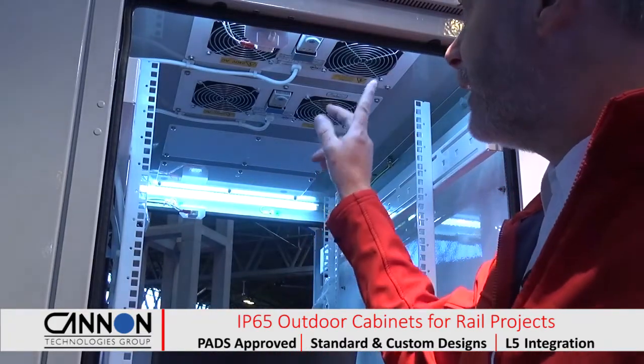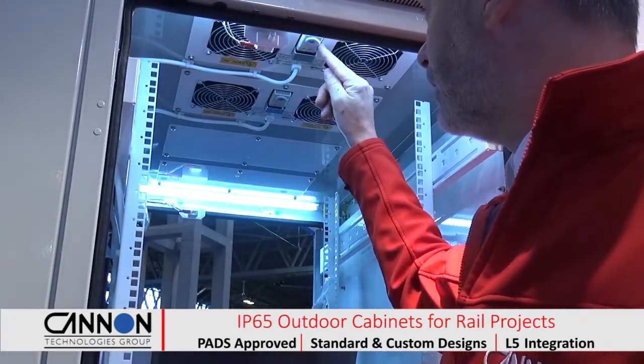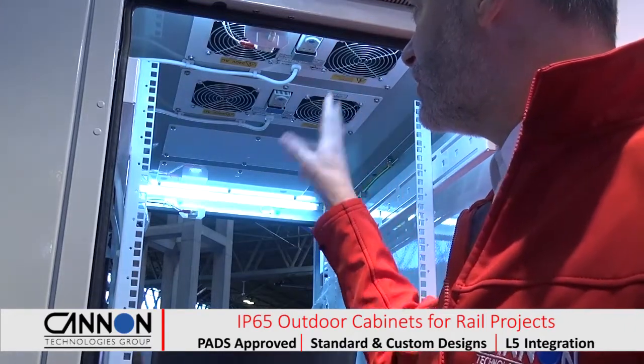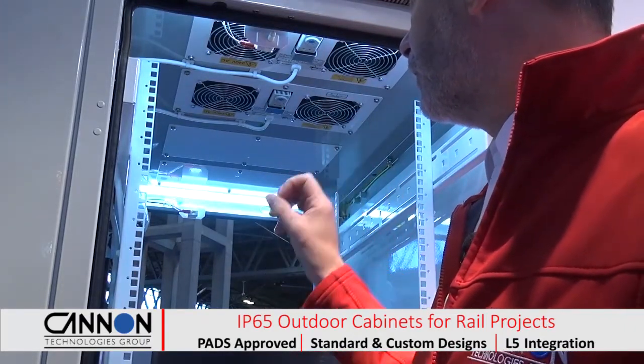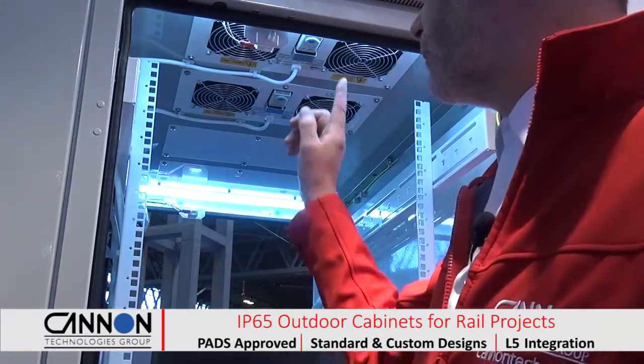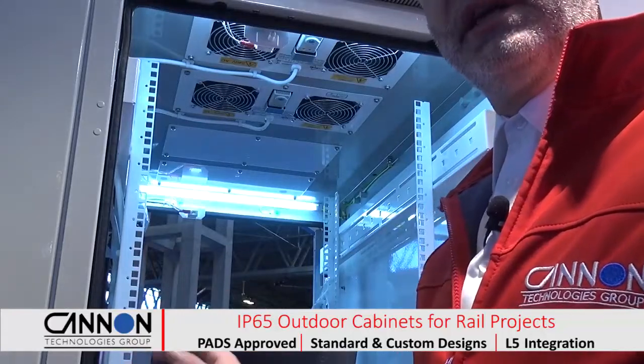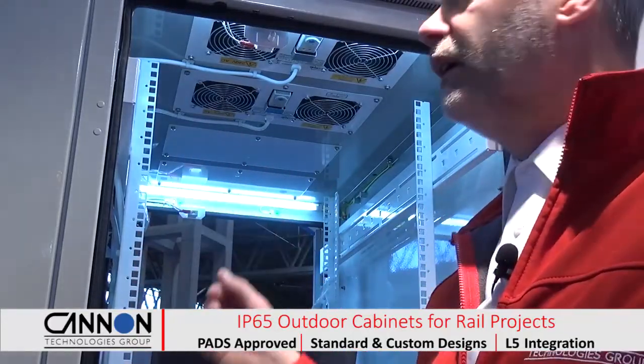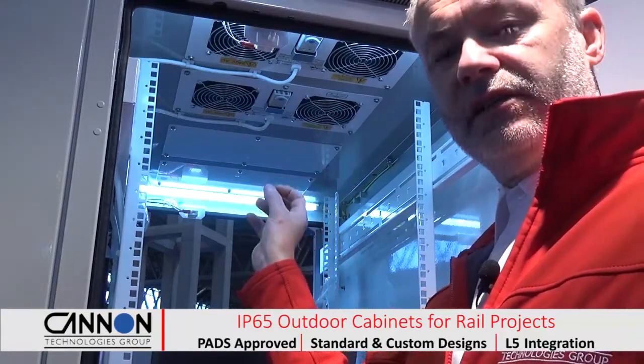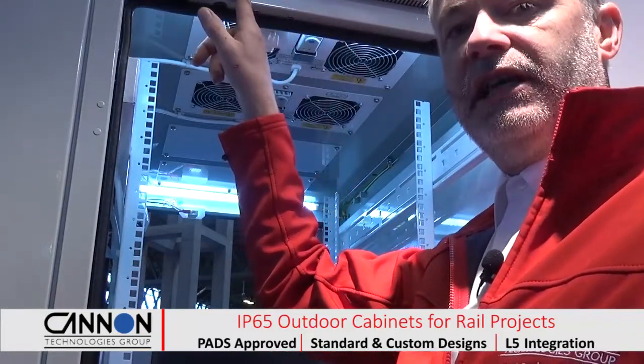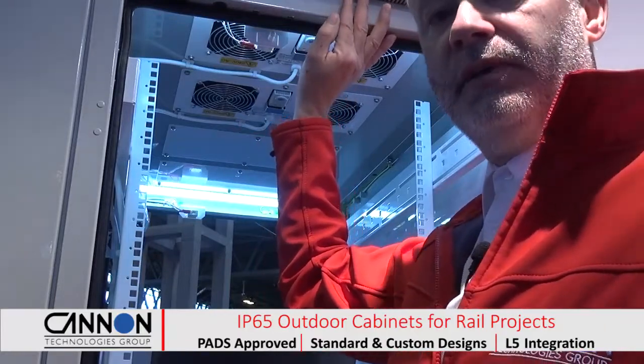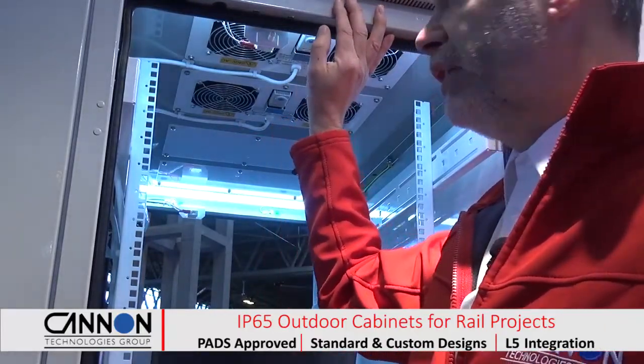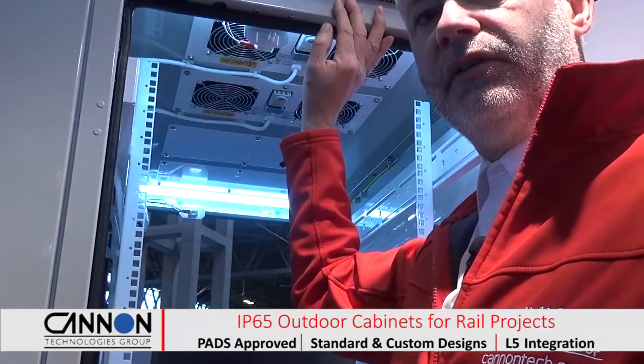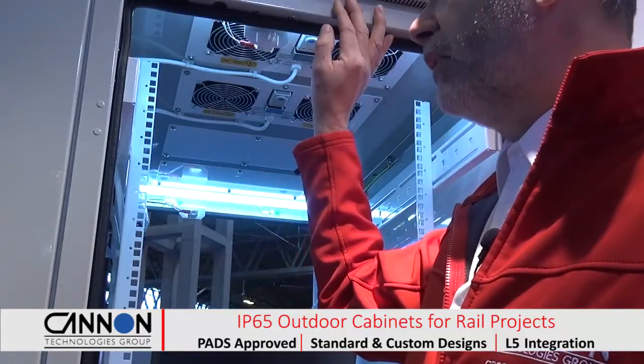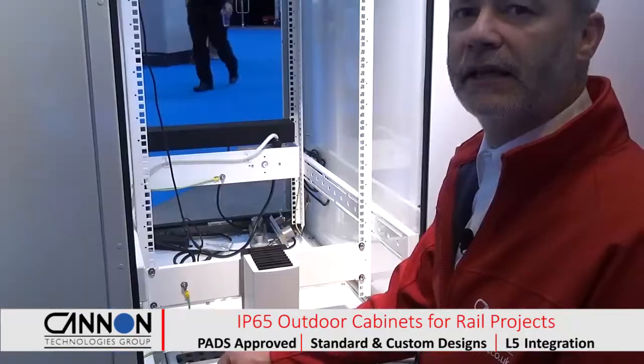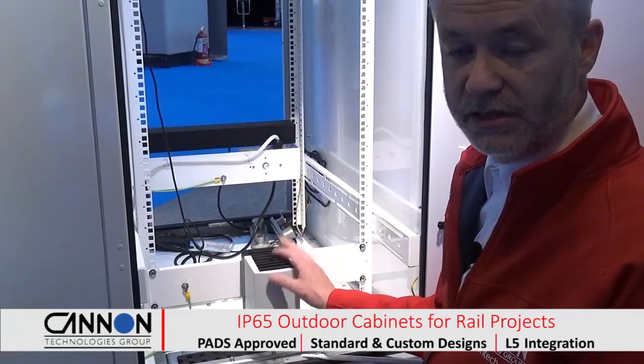So here we can see the top fan tray. This is controlled by mechanical electrical thermostats. These are a 230-volt system, but it provides additional cooling should it be required. As I said, we set the thermostats to the set temperature so we can draw as much heat out as possible. The fans are sucking the air and blowing it back out through the roof section here into slots, and you can feel a high degree of forced air coming out of there. So we're looking at probably cooling within 1.5 kilowatts, something like that, depending on the delta T and the ambient air temperature. But it does provide a high degree of cooling. As I said, this is the actual heater, and we do some calculations to size the heater.